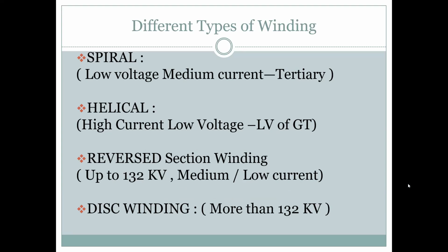Then helical winding, where there is high current and low voltage. This is the LV winding normally of generator transformers, where generally 11 kV, 3.3 kV, 6.6 kV voltage is generated by the turbine and generator, and then it is stepped up. So those transformers are getting low voltage and stepping up, so helical winding is useful. Reverse section winding is for 132 kV, medium/low current.